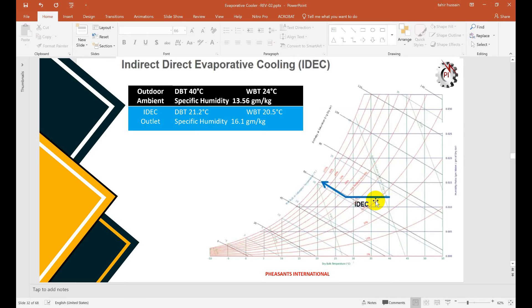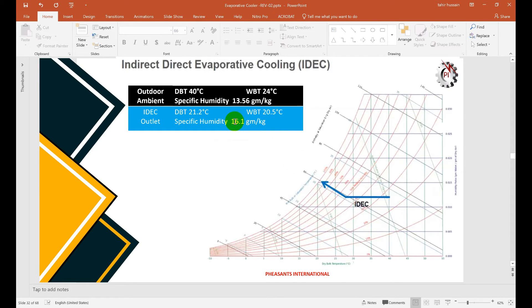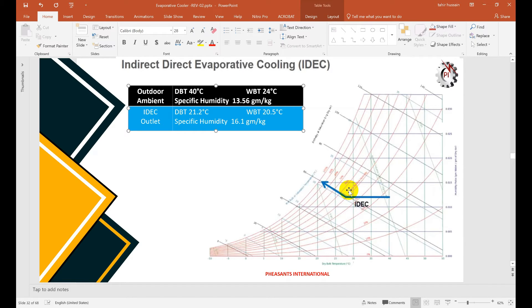In the combined IDEC process on the psychrometric chart: the first stage — passing through the heat exchanger — reduces sensible heat along a constant specific humidity and dew point line. The second stage uses the conventional direct evaporative (DEX/cellulose pad) system where wet bulb temperature and enthalpy remain constant. The specific humidity increases from approximately 13.56 to 16, but this moisture addition is less than in a single-stage direct evaporative cooling system.